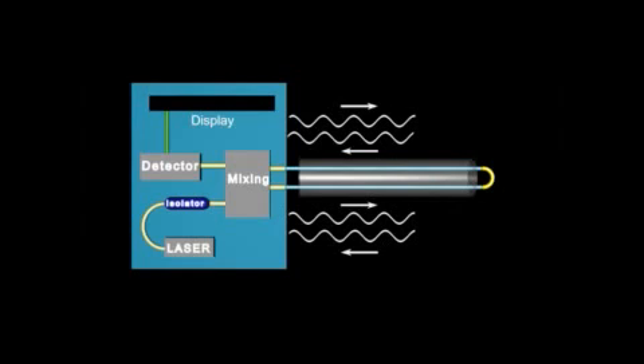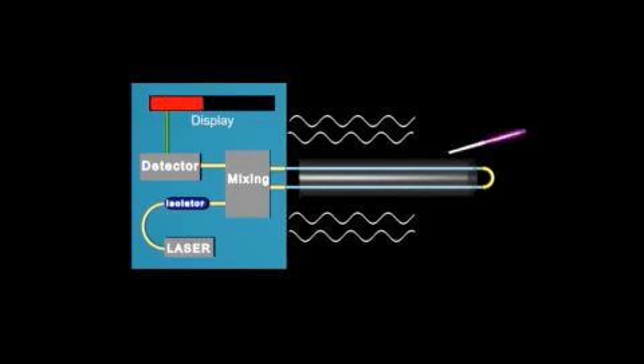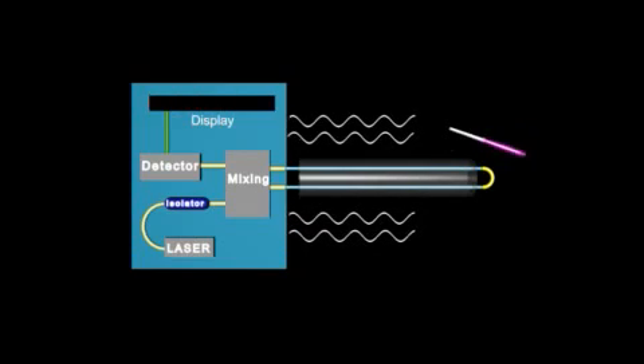However, an optical isolator prevents returning light from entering the laser's optical cavity, which would cause system instability. Under steady state conditions, the interference pattern would not change along the fibers, and the detector would see the same intensity of light over time. However, if the cable is bent, moved, or even tapped with a solid object, microbending slightly changes the optical path length the laser beams are traveling in.